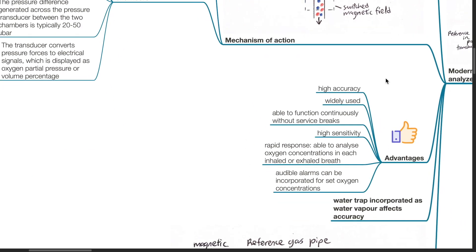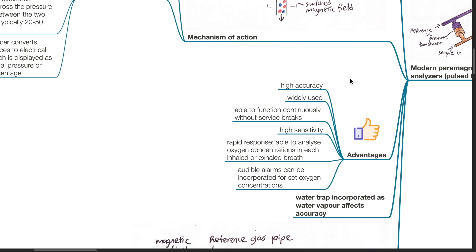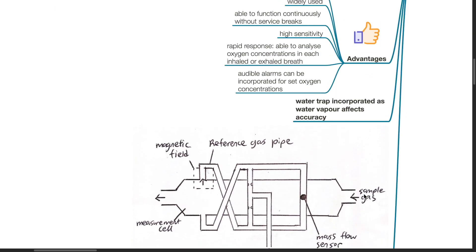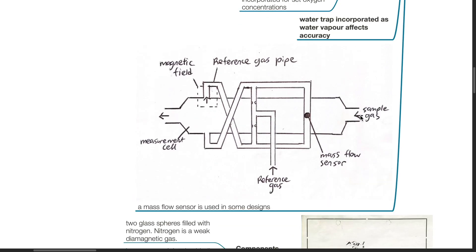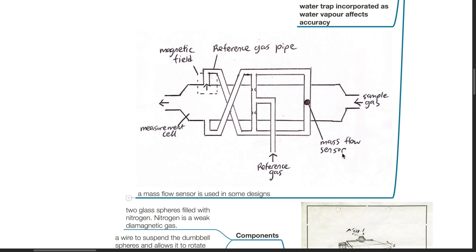Advantages of the modern paramagnetic oxygen analyzer: it is highly accurate and widely used, able to function continuously without service breaks, and has high sensitivity and rapid response, able to analyze oxygen concentrations in each inhaled or exhaled breath. Audible alarms can be incorporated for set oxygen concentrations. A water trap is incorporated as water vapour affects accuracy, and a mass flow sensor is used in some designs.